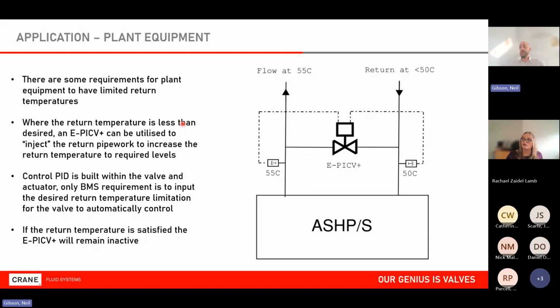So what they ended up doing is installing a solution where these valves were used to monitor the flow and return temperature. And if this return temperature was set at 50 via the valve, and if it dropped below 50, it was configured that the valve would open, bleed in some of the flow back into the return to top up this temperature from the 45 degrees. Now, it's a bit wacky, this example, because we're effectively generating energy to try to save the heat pump, which seems like a bit of a waste.